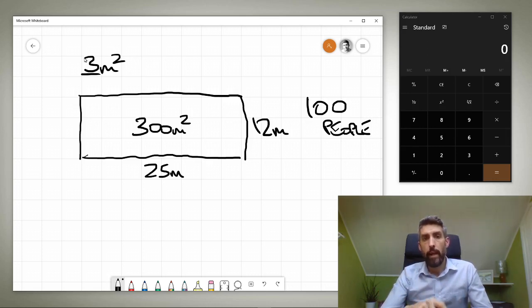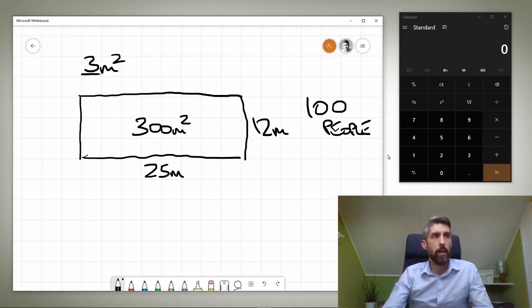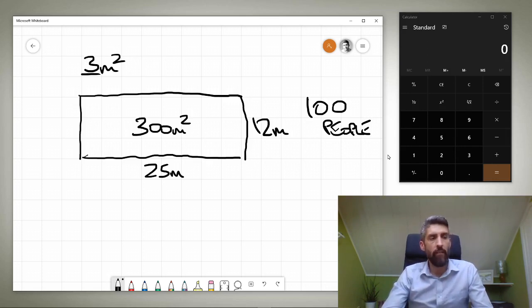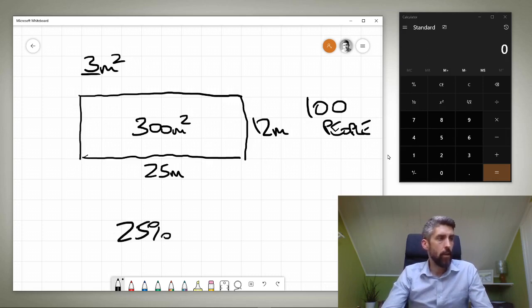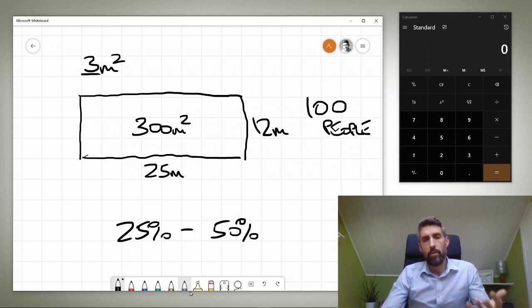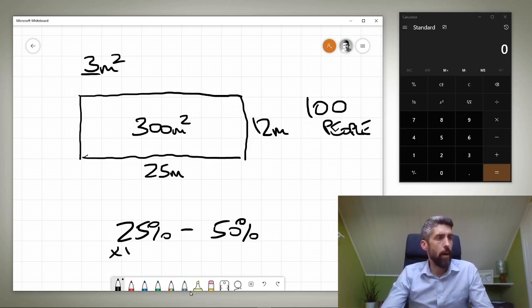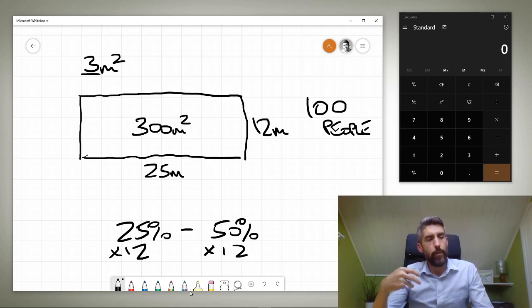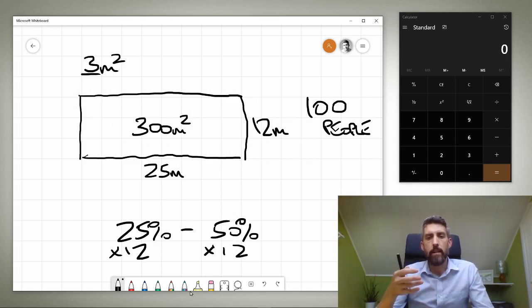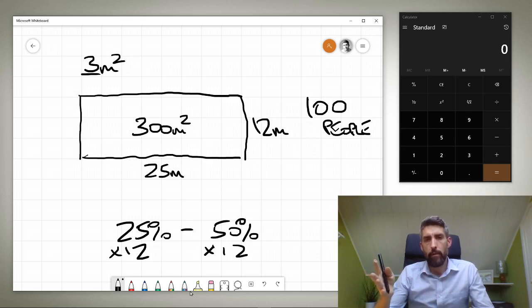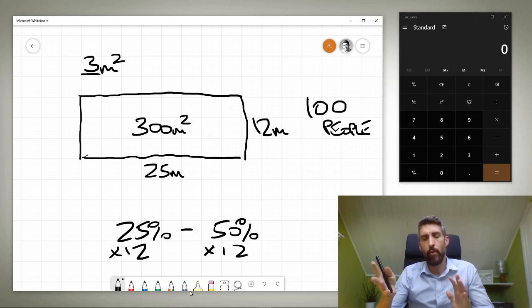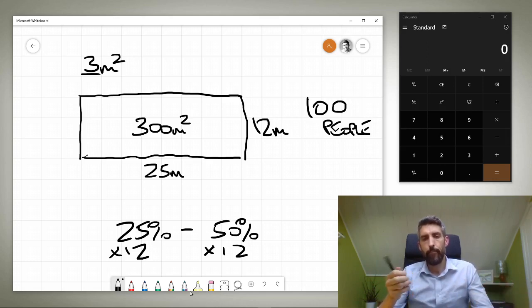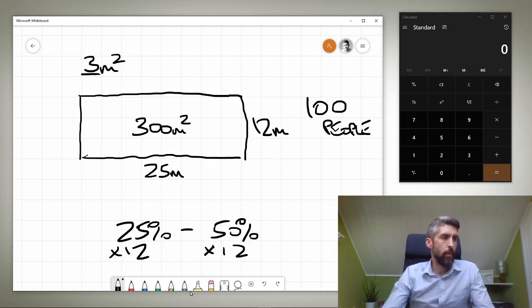In order to work that out, you take your instantaneous bathing load that we've just worked out, which is 100, and the formula for this is basically 25% of 100 to 50%. So it just happens to be a nice round figure that we've ended up with. So it's 25 to 50% and then you multiply by 12. The 12 is a bit of an arbitrary number. It's basically what is taken to be the average day that a pool would be open. If your days of operation are 16 hours a day, then you can multiply by 16, but let's go with this that we've got here at the moment.